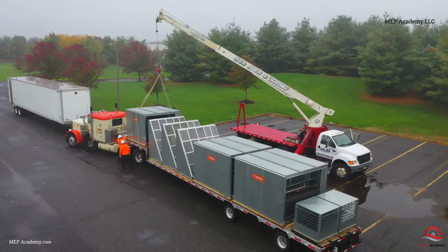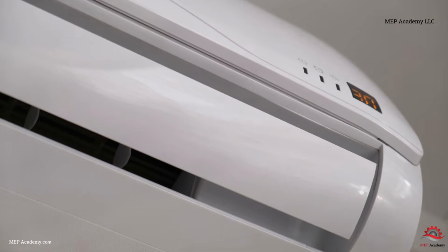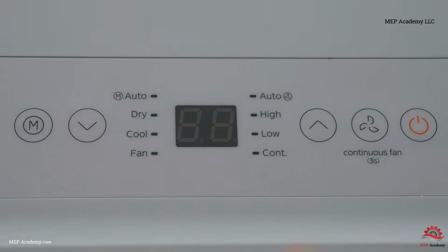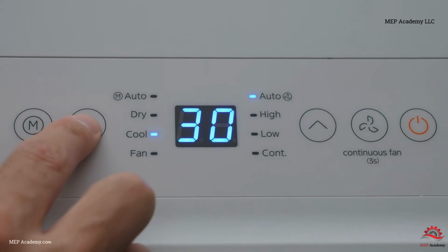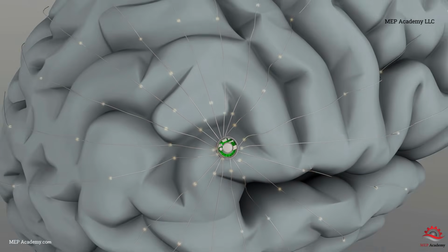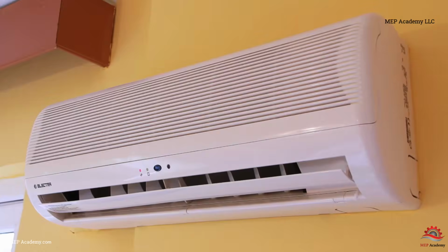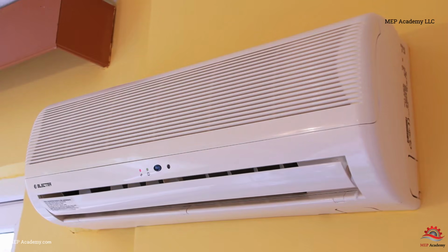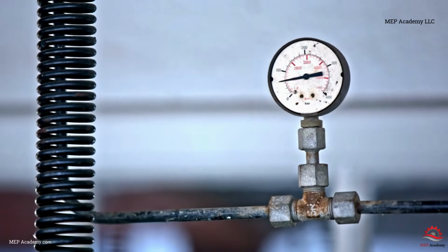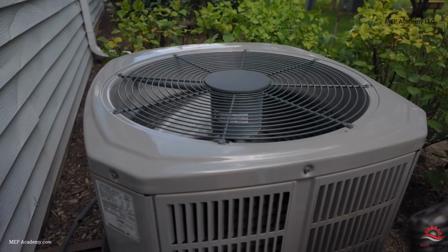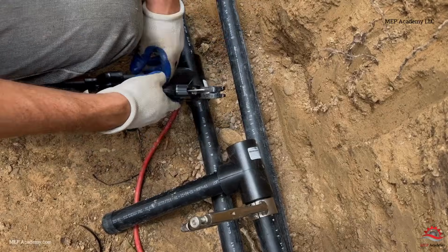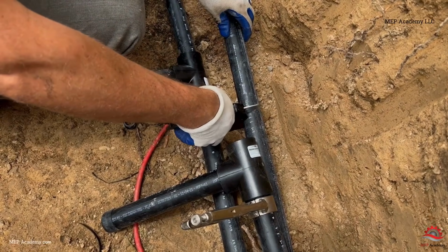One common cause is oversized equipment. An oversized unit cools the building quickly and shuts off before enough moisture can be removed. This is known as short cycling. Other causes include excessive outdoor air, economizer problems, building pressure issues, control problems, or inadequate reheat strategies. The solution depends on identifying the source.